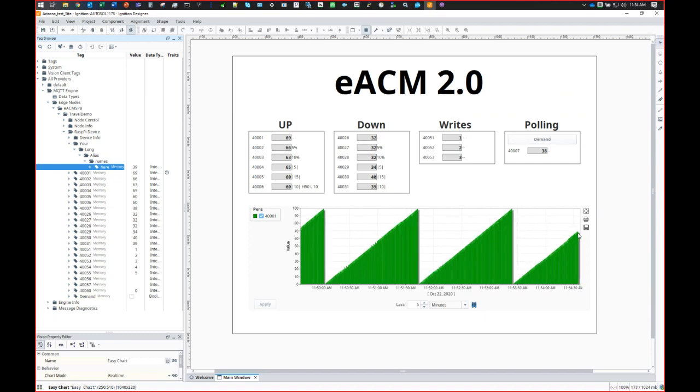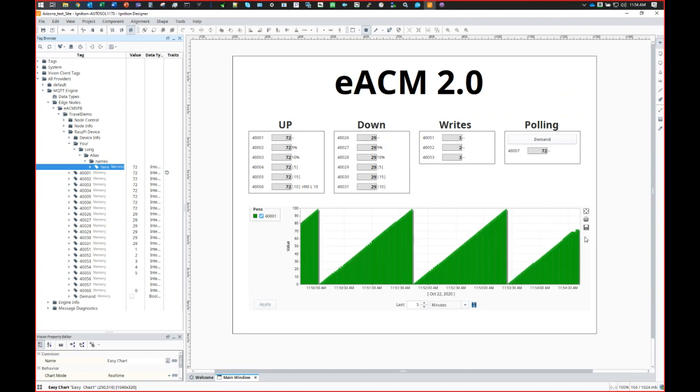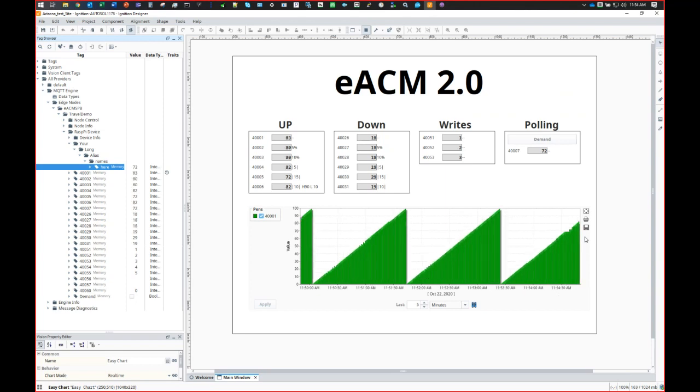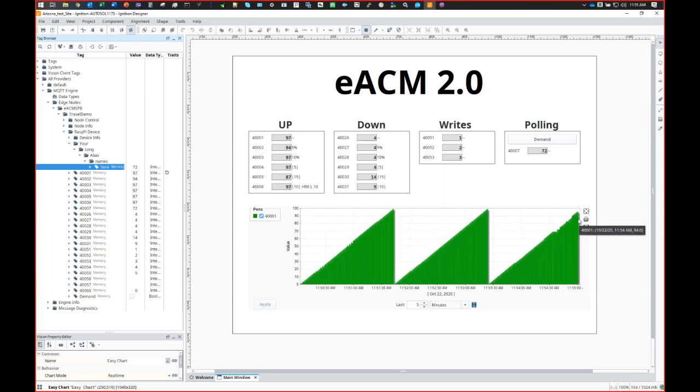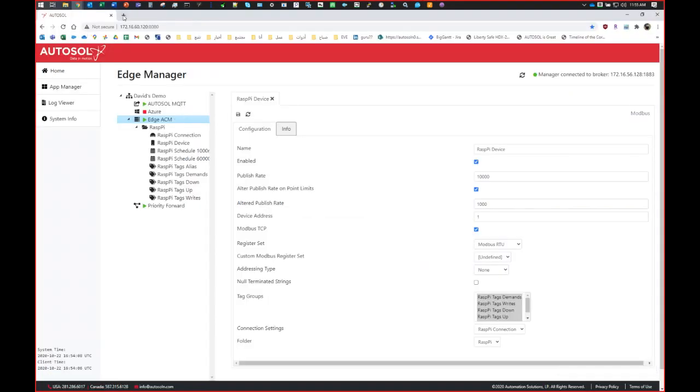this guy is going to flatten out, but every 10 seconds, I'm going to get a package of 10 values, 1 current value and 9 historic records. So after 10 long seconds of dead air in a demo, there we go. So this guy just updated with all 10 of those values. So the answer to your question is yes, you can gather faster than you publish, and when you publish, you're going to send it bundled in with this message.